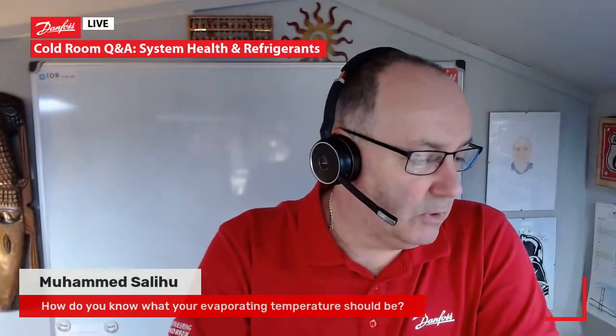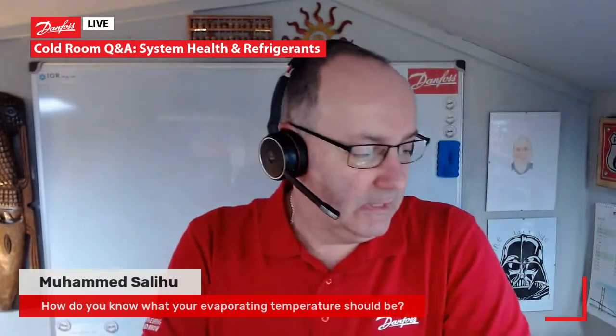There are many books and pieces of literature that will explain your temperature difference, evaporating temperature, etc. Generally, if you want something like 80% humidity, and I'm just looking down at some of the notes that I've used over the years, you want roughly 8 to 9 Kelvin difference between your evaporating temperature and your room temperature. If you want a very low relative humidity, then you want something like a 10K temperature difference. So if you had a room of +5, you'd be evaporating at -5, so you've got that 10K difference.